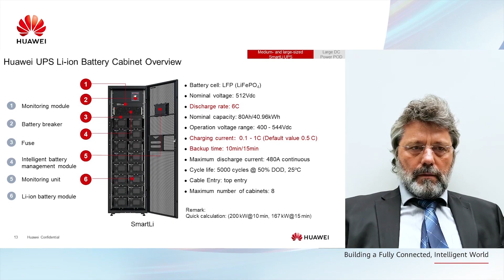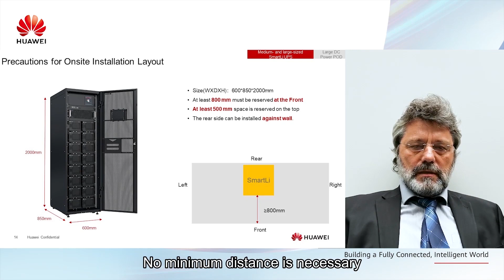This slide shows the overall dimension and the layout of a lithium-ion battery cabinet. It is 600 mm wide, 850 mm deep and 2000 mm high. In the front, 800 mm service space is required. On the top of the unit we need to reserve 500 mm. On the right and left and rear side, no minimum distance is necessary.